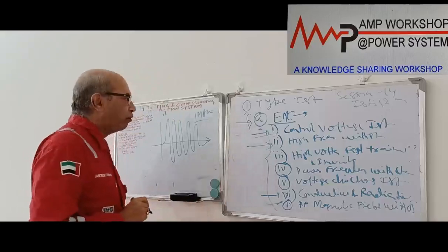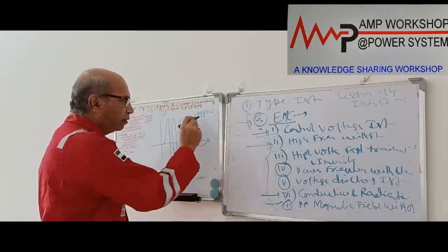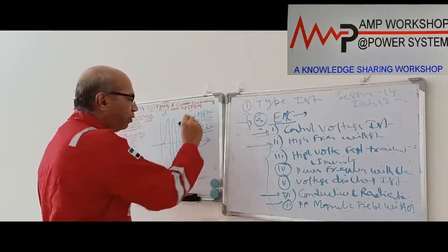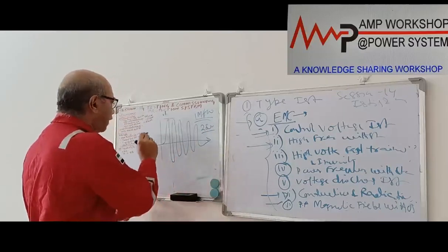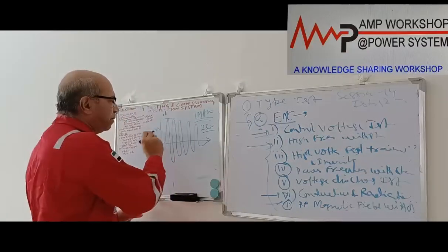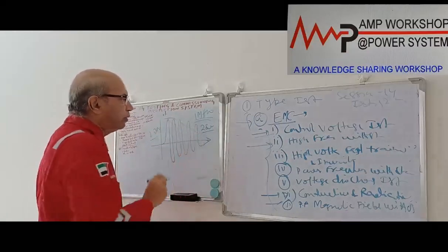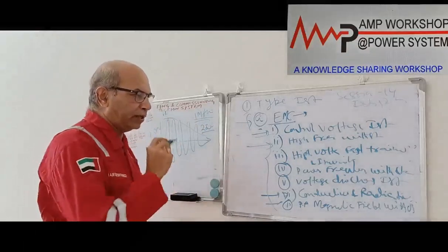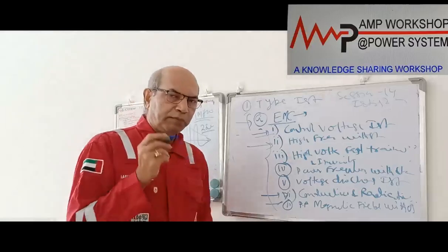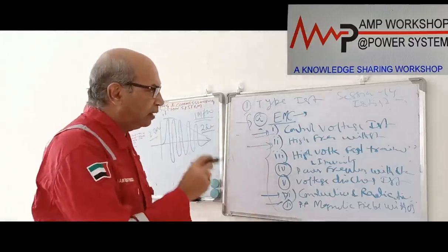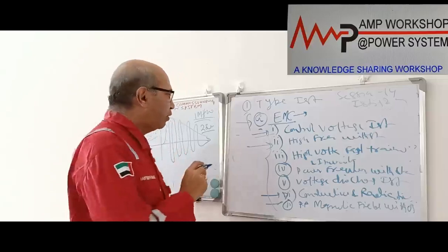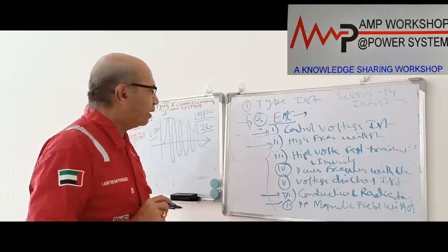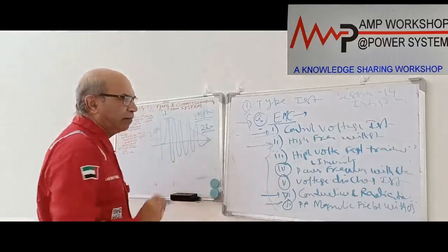We inject this 1 megahertz voltage signal for 2 seconds. The peak value will be 2.5 kV, then it is gradually decaying to 0, and the frequency is 1 megahertz. If this voltage is injected to the input port, that is the CTPT port, then this relay should not maloperate. That's why we check this high frequency withstand capacity of this device. This voltage is a gradually decaying voltage.